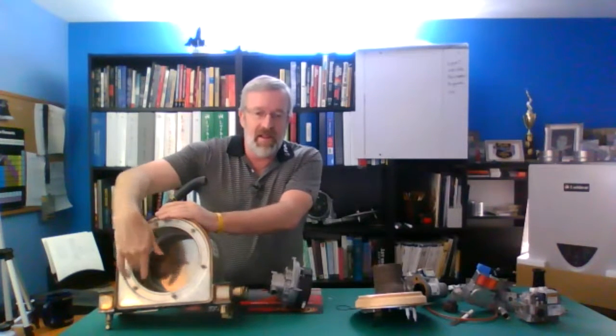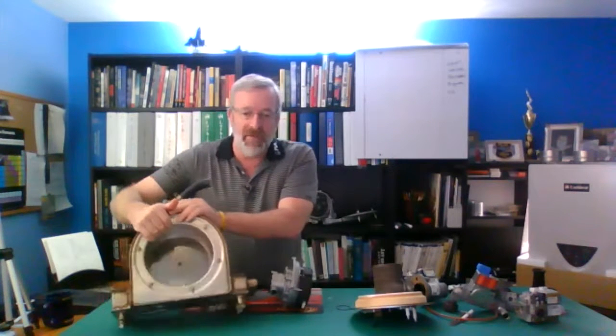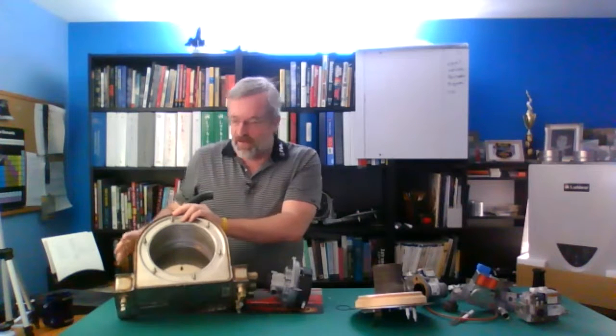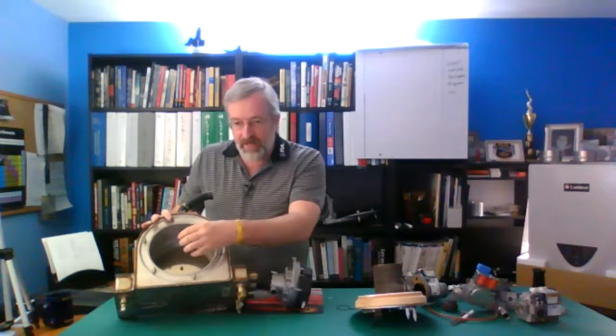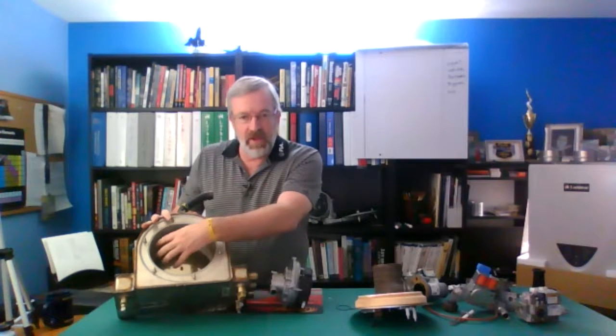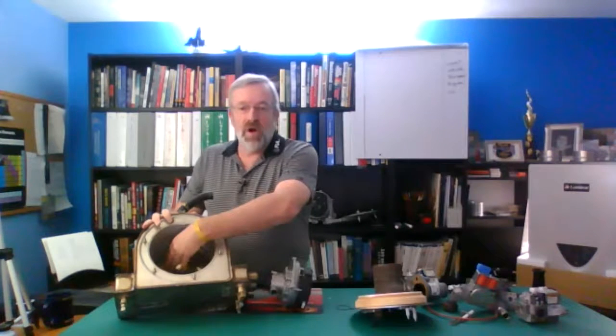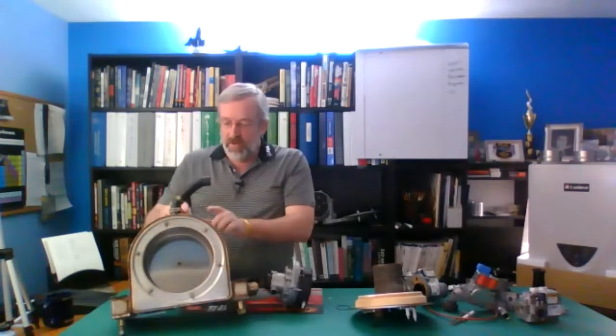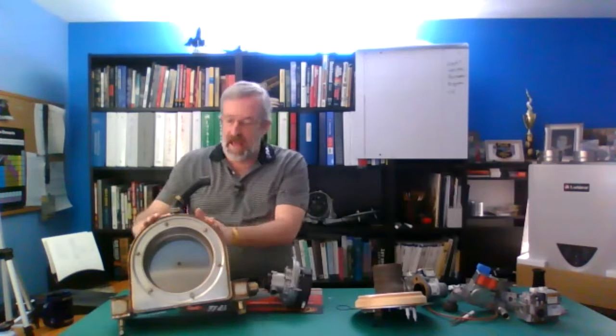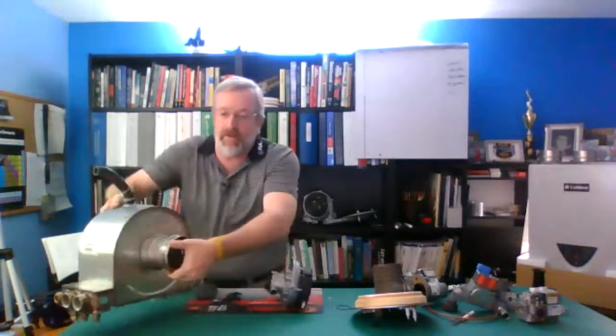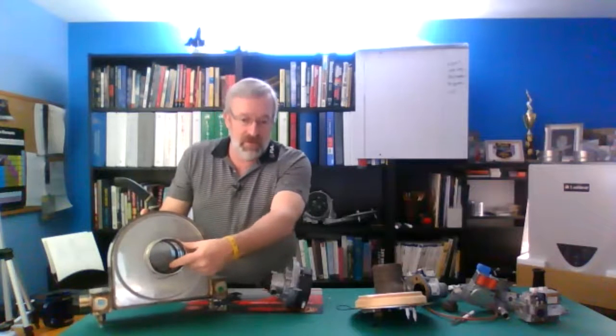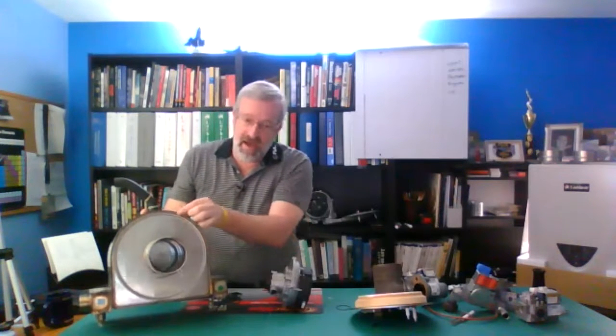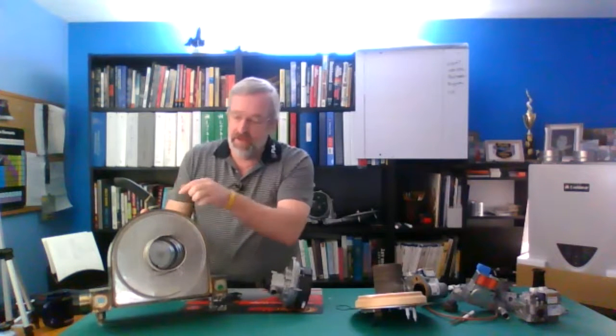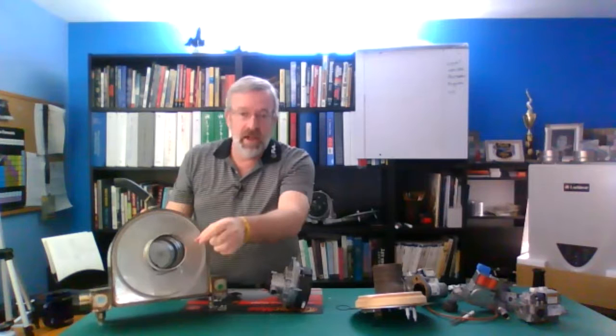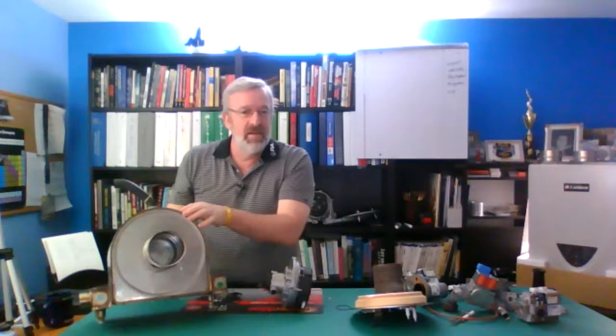And that is getting in here and cleaning this in between these tubes. What we don't want to have is buildup in the tubes. The design of this heat exchanger is that my air movement is in between these tubes. As I do it, that goes through there. This wall here is not all the way at the back. So as I go out through those tubes, I'm on the inside of this outer wall, if you will. There's a space, there's a cavity for that. And as you can see, that wall that we're looking at allows the air to kind of move down here on the back through another set of tubes, and then goes out through there. So that's how we're getting all the energy out of there.